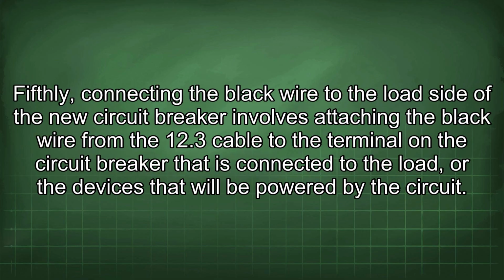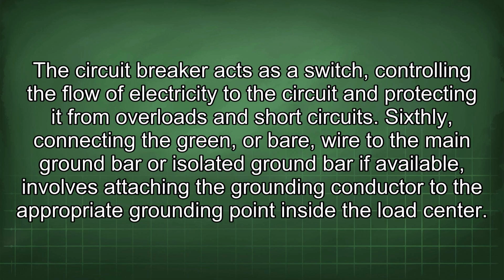Fifthly, connecting the black wire to the load side of the new circuit breaker involves attaching the black wire from the 12-3 cable to the terminal on the circuit breaker that is connected to the load, or the devices that will be powered by the circuit. The circuit breaker acts as a switch controlling the flow of electricity to the circuit and protecting it from overloads and short circuits.